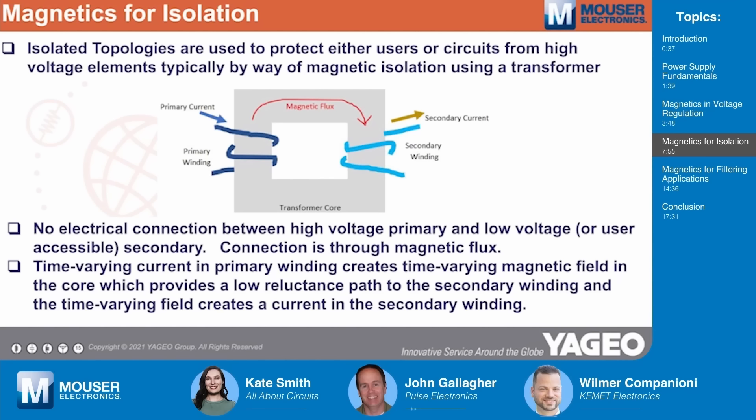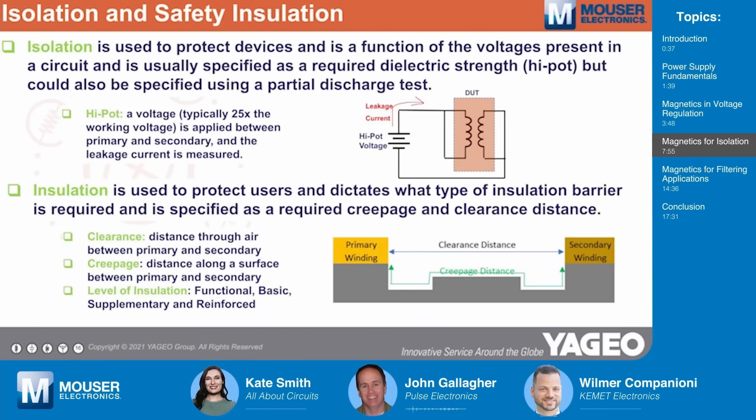This happens across a variety of topologies — flybacks and forwards, half bridges, push-pulls, phase-shifted full bridges — but the magnetics used all follow the same basic principles. It's important when talking about isolation to differentiate between isolation and safety insulation, as the two terms are often used interchangeably, which leads to confusion. Isolation is used to protect devices and is a function of the voltages present in the circuit. We typically define a hi-pot spec at about 25 times the actual voltages in the circuit — so for a 48-volt circuit, you might have a 3000-volt hi-pot spec — to stress the part much higher than it will see in operation.